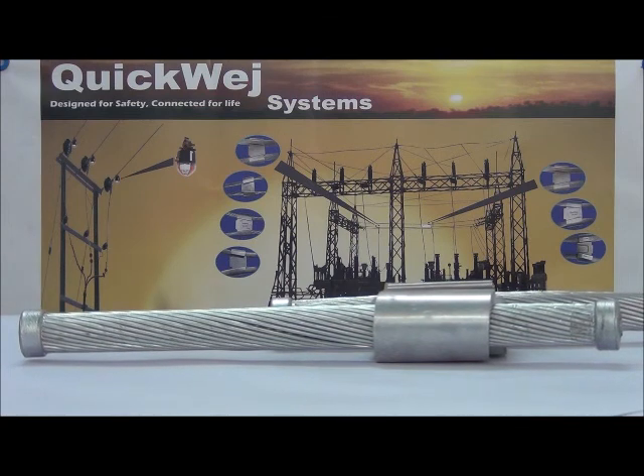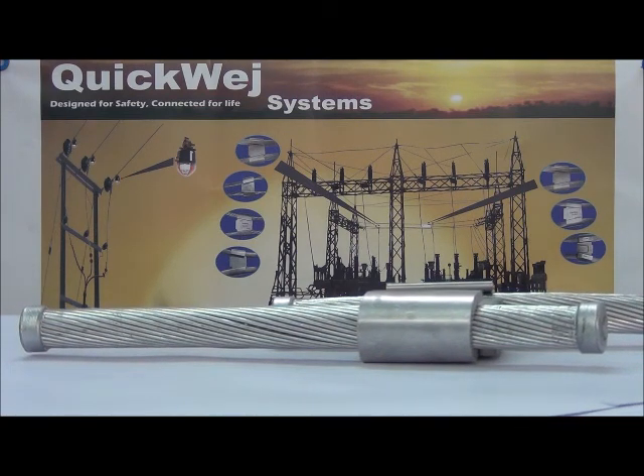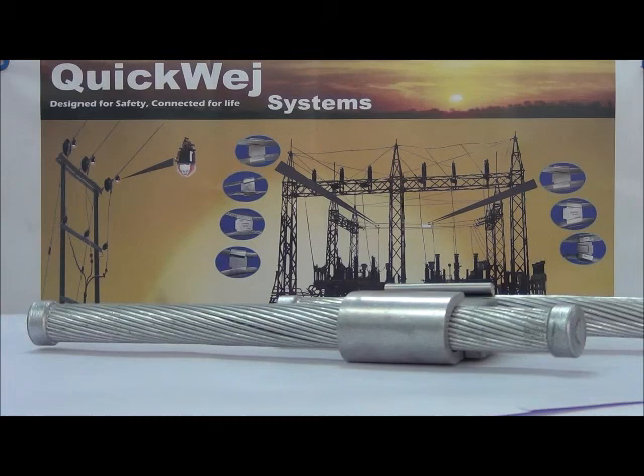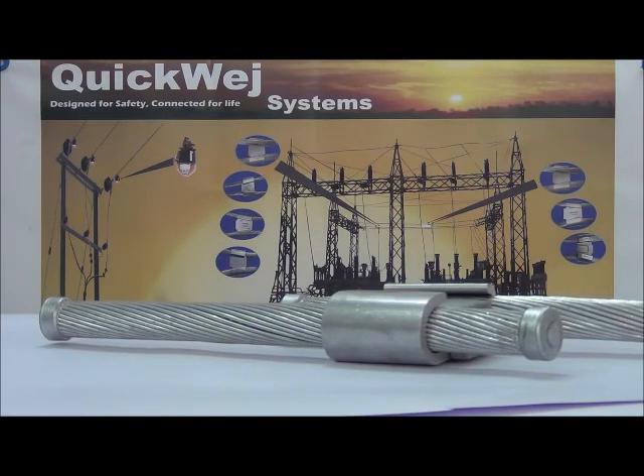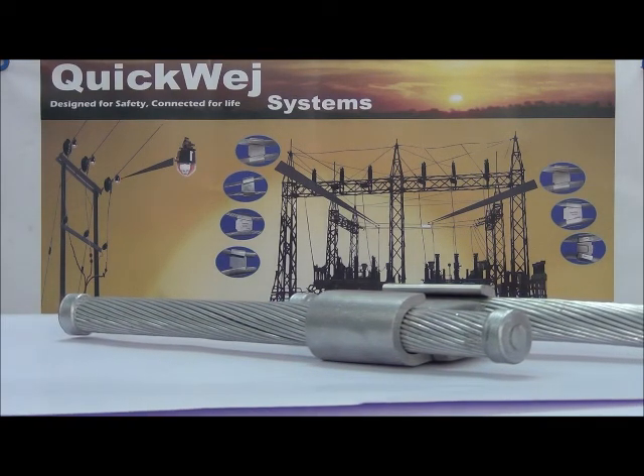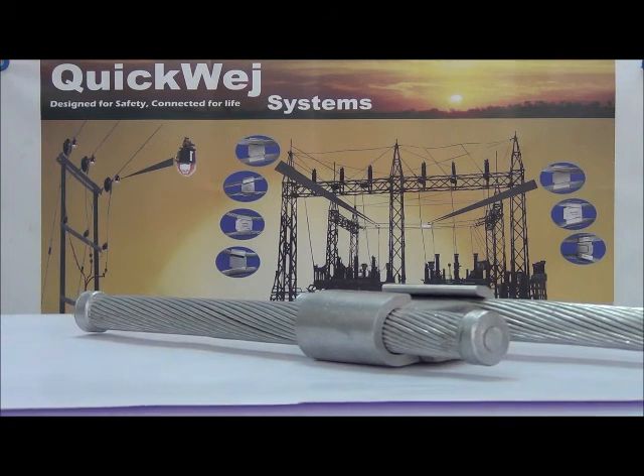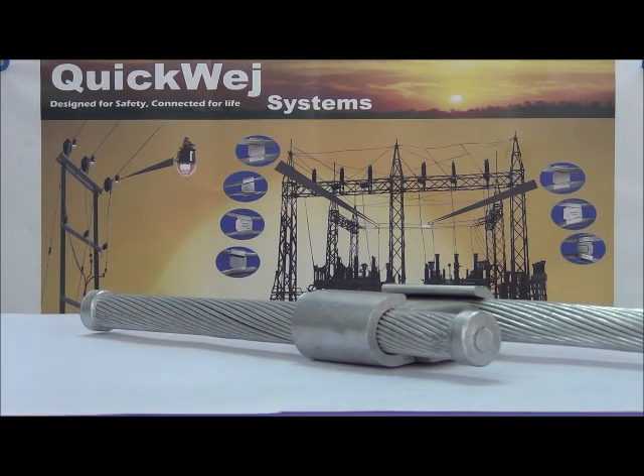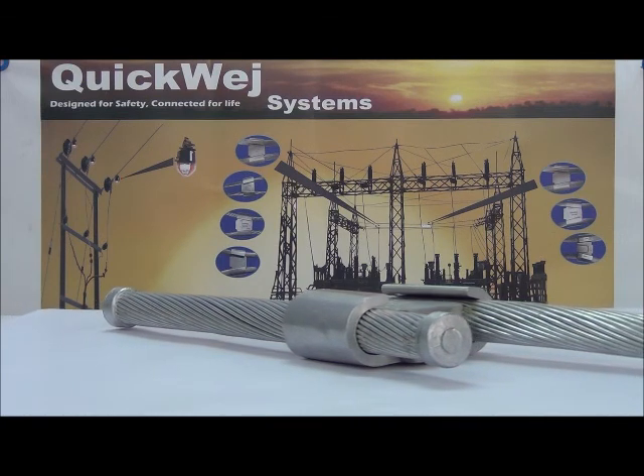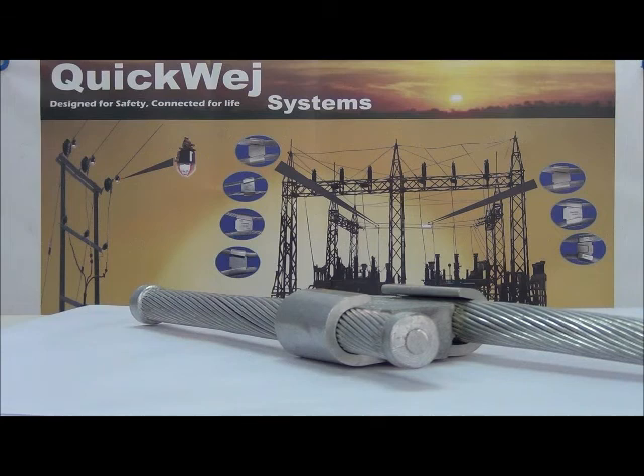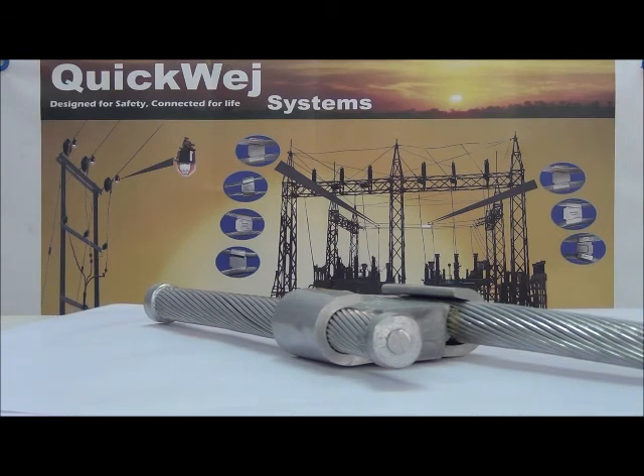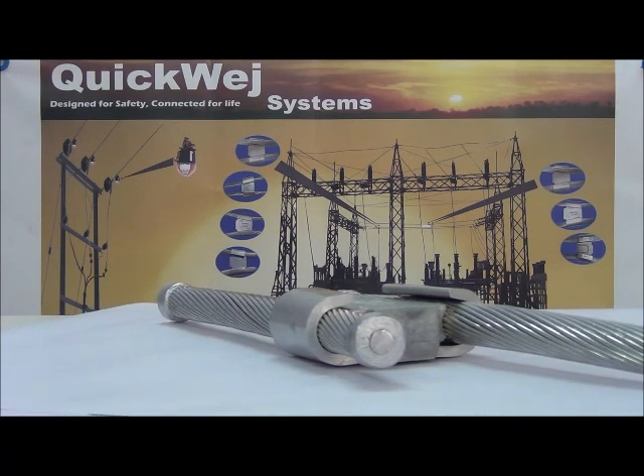QuickWej finds applications in substations, transmission lines, and distribution networks. QuickWej is a non-tension connector which can be used for jumps, jumpers, taps, and to connect conductors to equipment like CTs, PTs, lightning arresters, isolators, circuit breakers, and transformers. QuickWej is also available for twin conductor combinations.